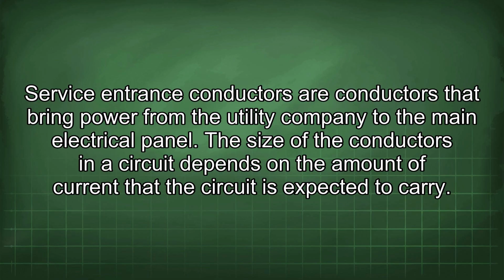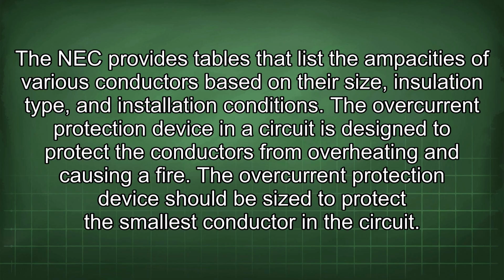The size of the conductors in a circuit depends on the amount of current that the circuit is expected to carry. The NEC provides tables that list the ampacities of various conductors based on their size, insulation type, and installation conditions. The overcurrent protection device in a circuit is designed to protect the conductors from overheating and causing a fire. The overcurrent protection device should be sized to protect the smallest conductor in the circuit.